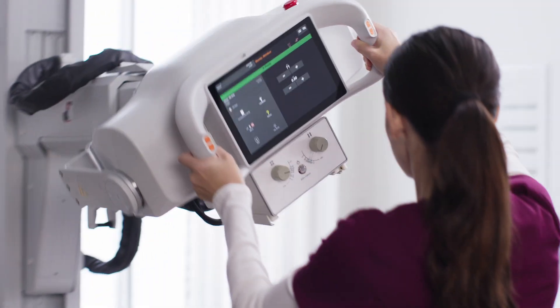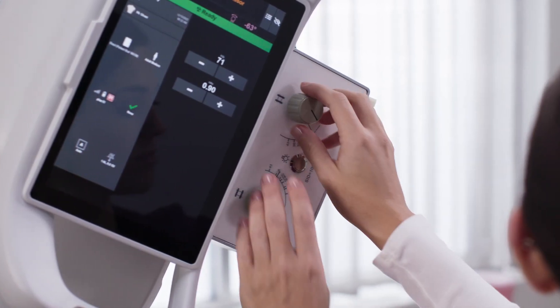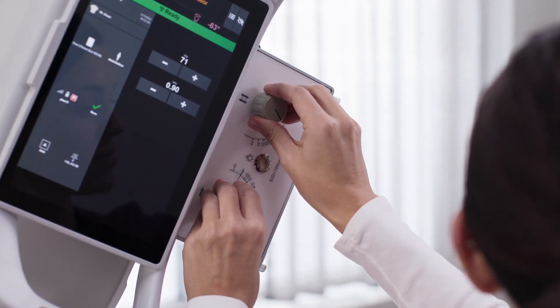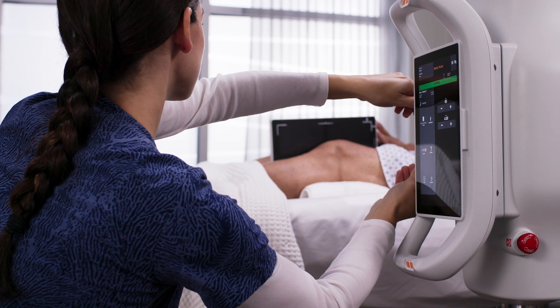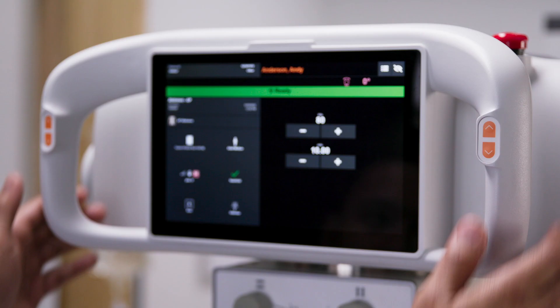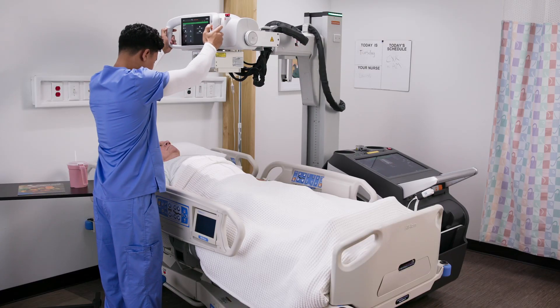The small tube is easy to control via two ergonomic handles and is equipped with rotational detents to aid with precise angulation. The manual collimator allows easy and smooth adjustment with bright LED lighting to ensure visibility of collimation borders, even in bright environments. To further maximize productivity, the system includes secondary drive controls on the tube head, allowing technologists to make small adjustments forward and backward directly from the tube head without the need to return to the cart — promoting greater convenience and faster exams.